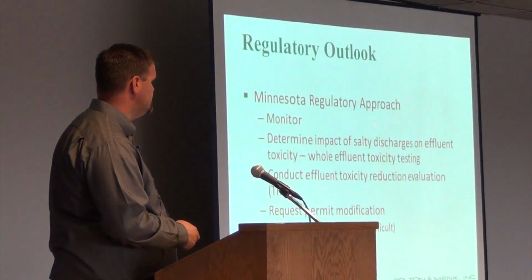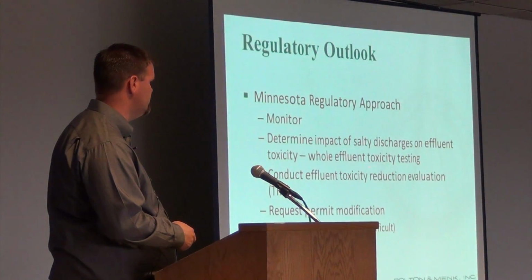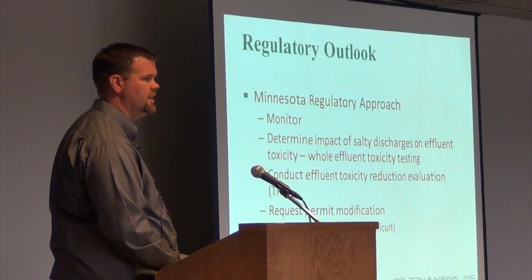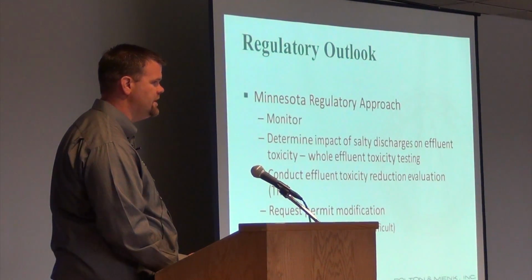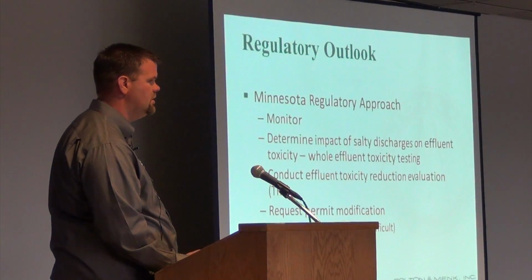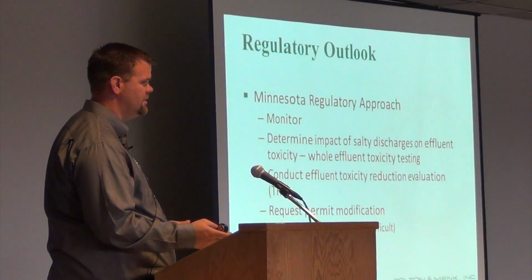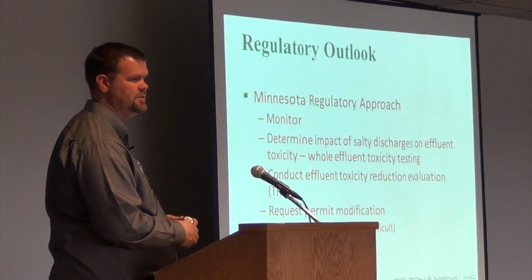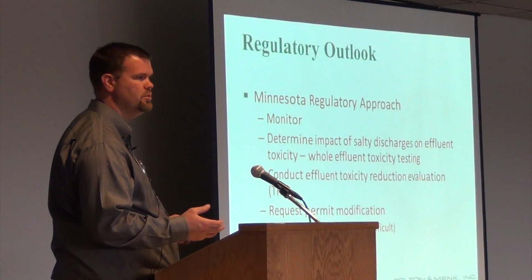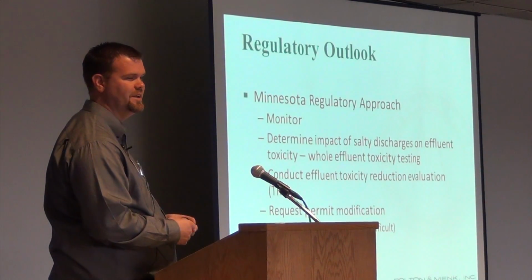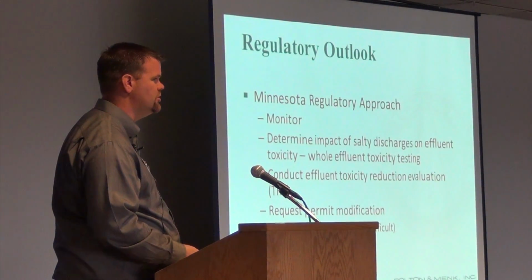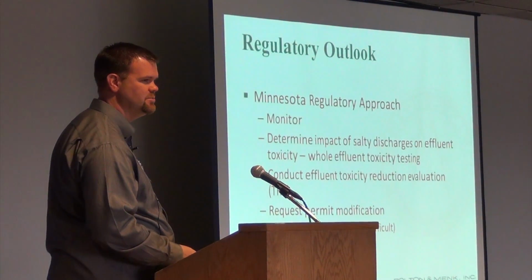The other thing that they've been doing, and that we've actually worked with a couple of our clients on, is whole effluent toxicity, or the WET test. That's a common test that wastewater plants do. They send in their wastewater, they put minnows and Ceriodaphnia in the water, and they see how they live, how they reproduce, and make sure everything's okay. It's a measure of anything that could be toxic to the organisms in the water.